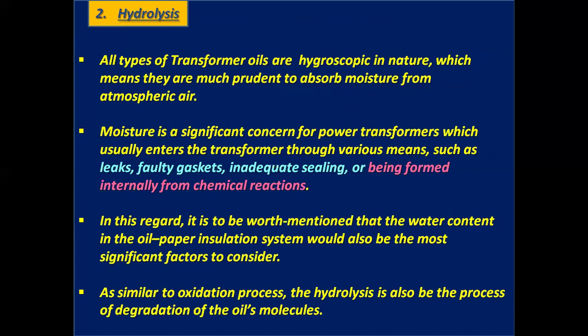hydrolysis. All types of transformer oils are hygroscopic in nature, which means they readily absorb moisture from atmospheric air. Moisture is a significant concern for power transformers, and usually enters the transformer through leaks, faulty gaskets, inadequate sealing, or is formed internally from chemical reactions.